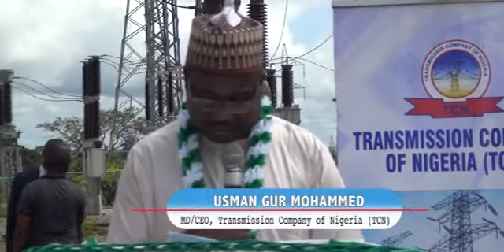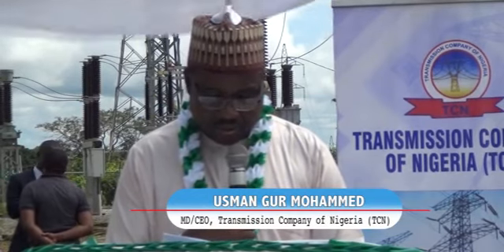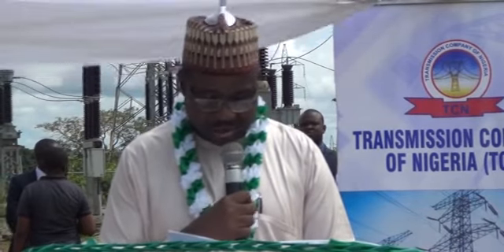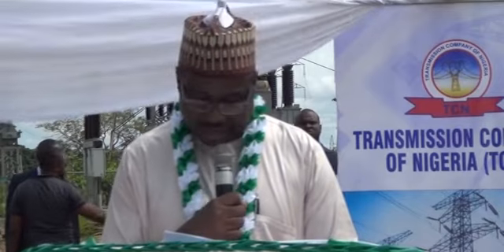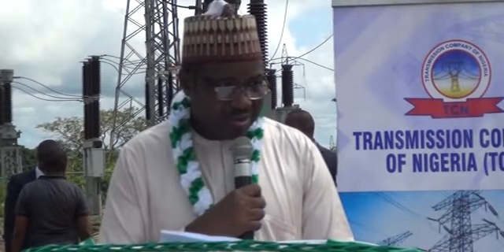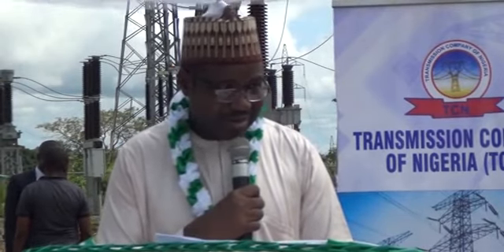As part of trend, milestones have been achieved here at Opela in Edo State. With the installation of 1x60 MVA transformer, the capacity of the substation, which was before now 15 MVA, has now been raised to 75 MVA. That means we have increased the capacity by over 300%.